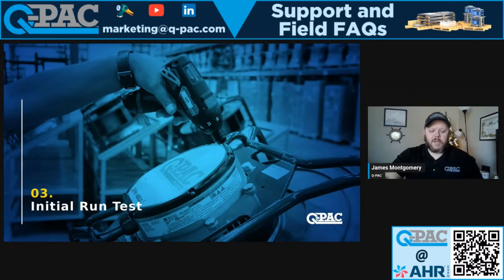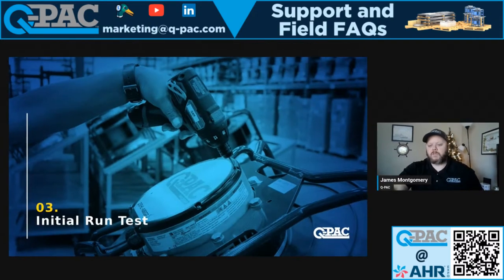All right, so the initial run test. We did the pre-startup. We checked a lot of things. We spun the fans. We made sure nothing was bad. We did that because when it comes time to start this, we don't want to see issues of rubbing or bearing issues or debris or anything like that. So now, assuming everything's good, we'll go to this initial run test.